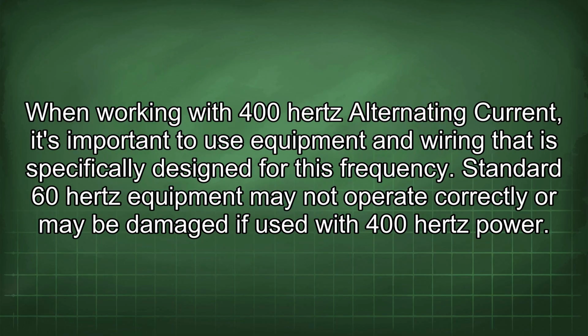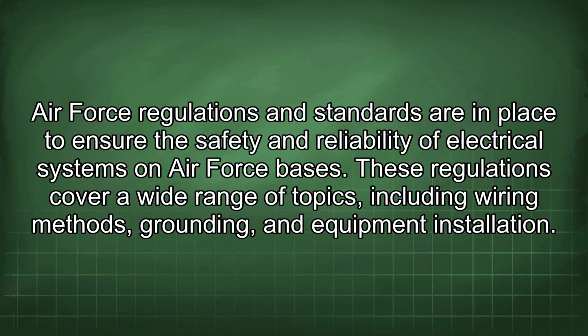When working with 400 Hz alternating current, it's important to use equipment and wiring that is specifically designed for this frequency. Standard 60 Hz equipment may not operate correctly or may be damaged if used with 400 Hz power. Air Force regulations and standards are in place to ensure the safety and reliability of electrical systems on Air Force bases. These regulations cover a wide range of topics, including wiring methods, grounding, and equipment installation.